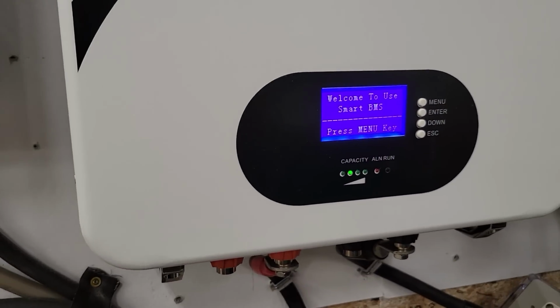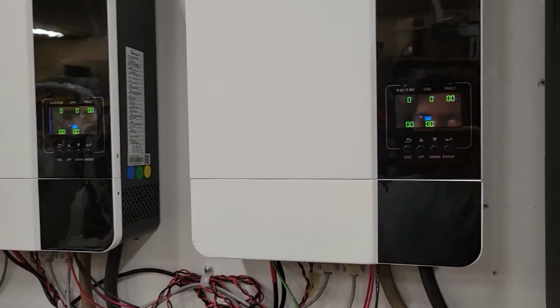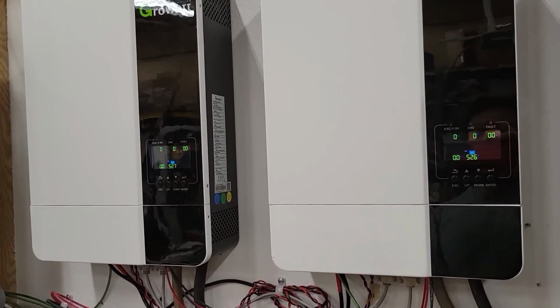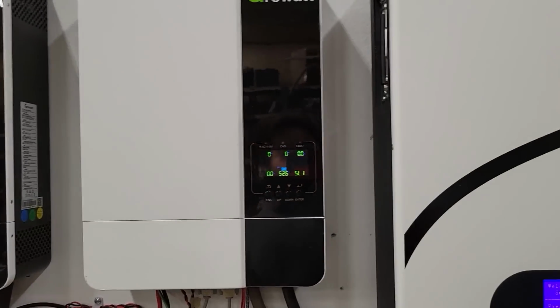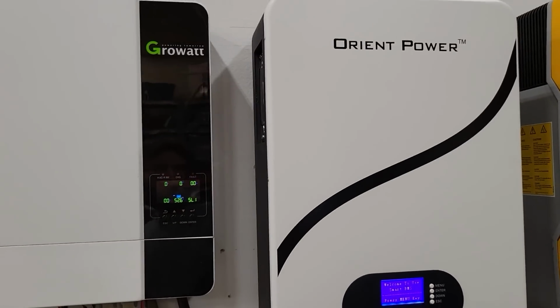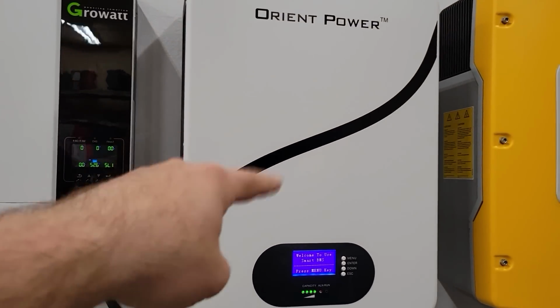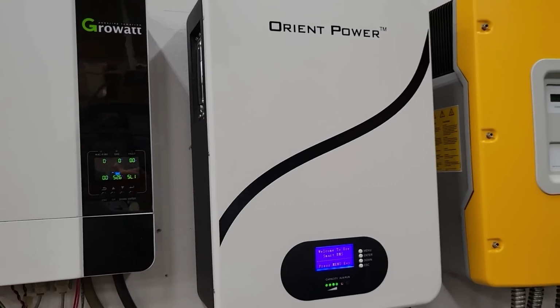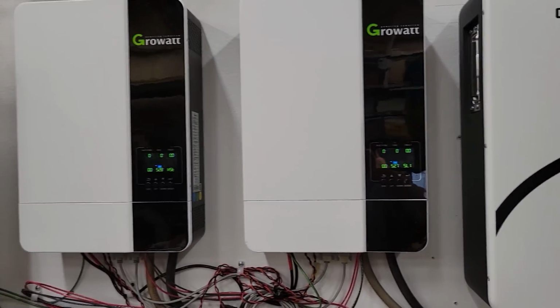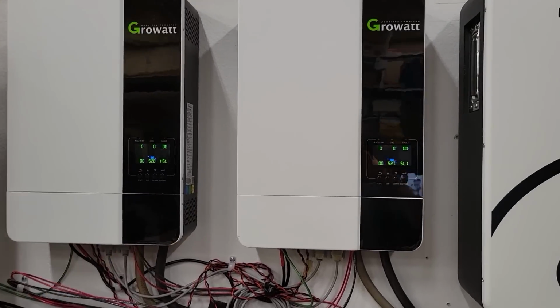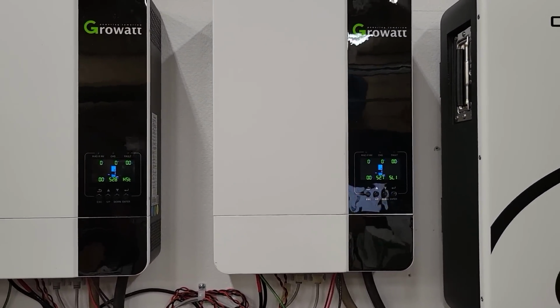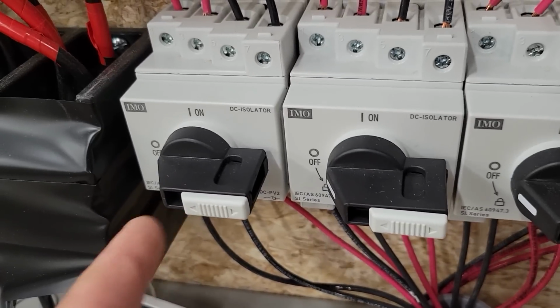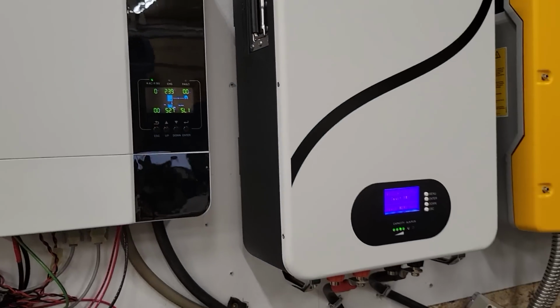Go, bring things back online. This is hard on these inverters, I hope I don't burn them out doing this test for everyone. It's not the battery's fault, we're just finding the limitations of the battery. But it is hard on the inverters to keep losing the DC voltage, and by the way, solar is turned off, so there's no solar input to assist.